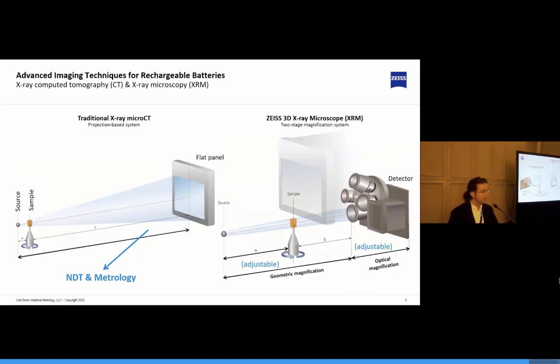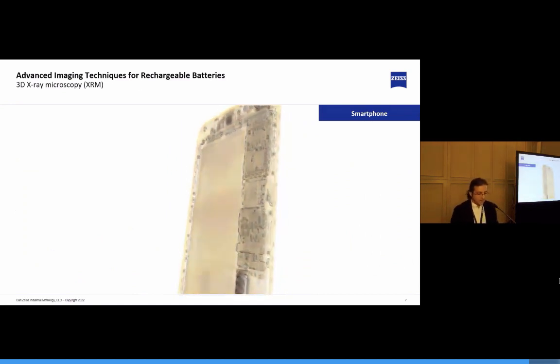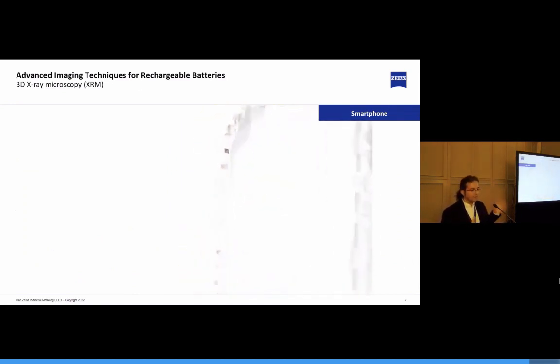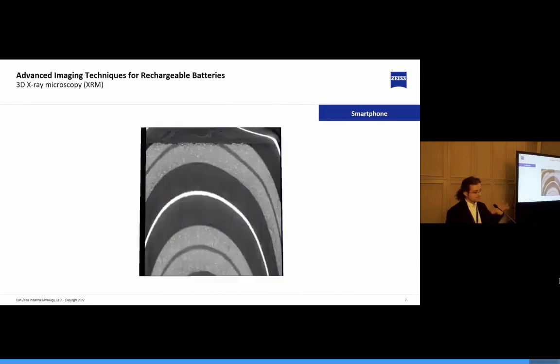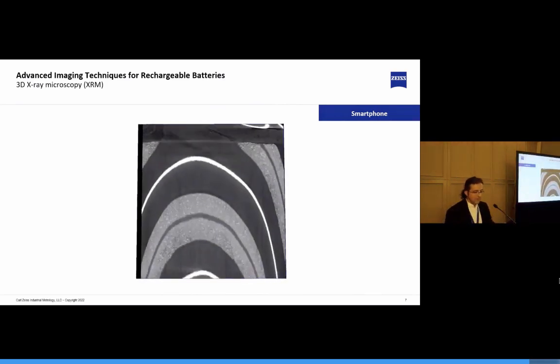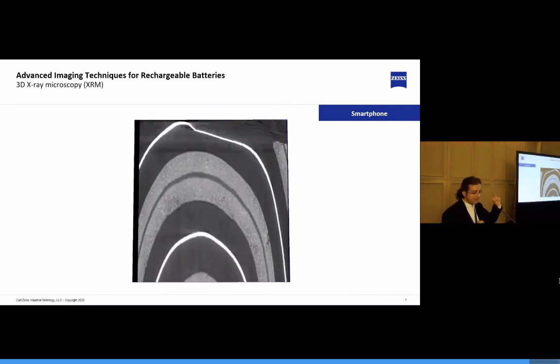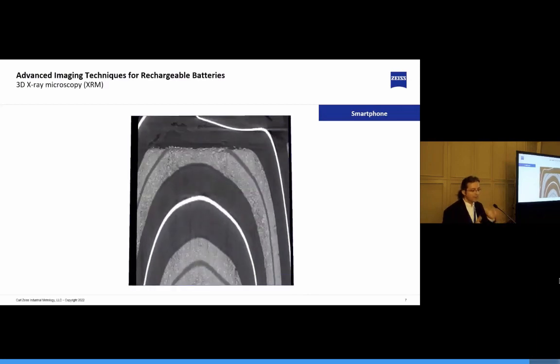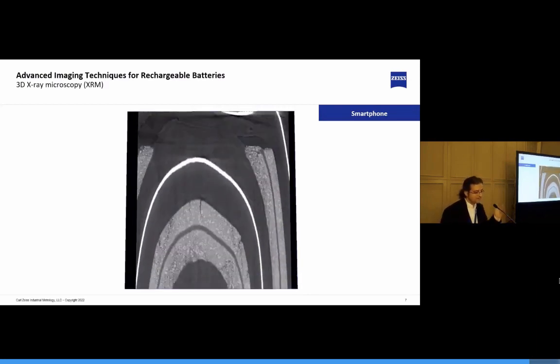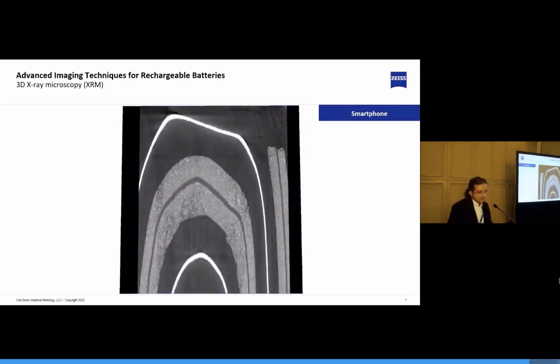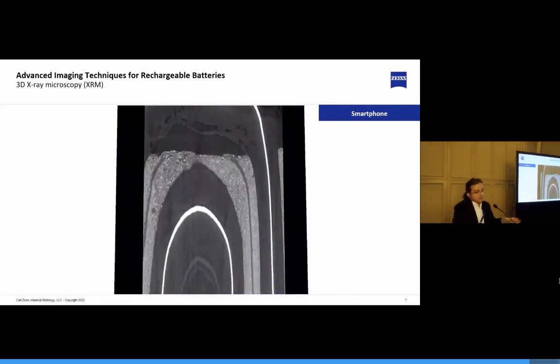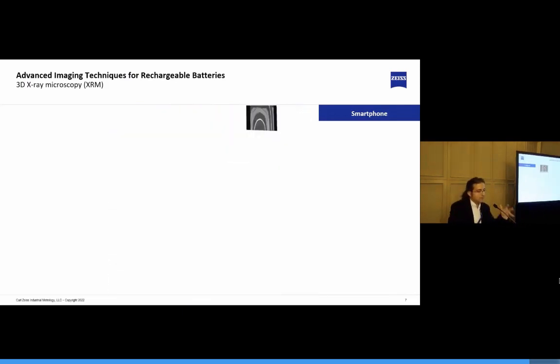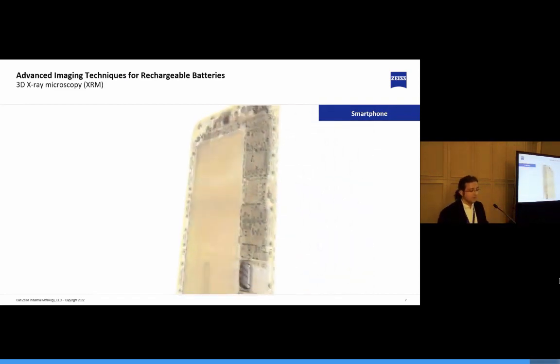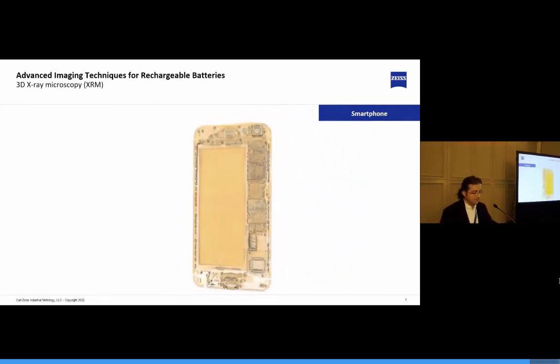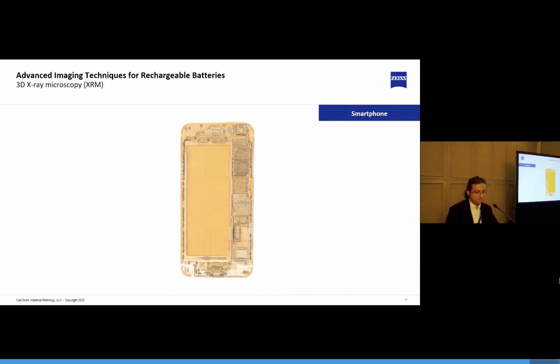This example shows how we can scan a full device, such as a smartphone, without destroying it. And then by zooming in with the lenses, we can scan small regions of interest, such as the smartphone battery, to look for any structural changes or degradation in different layers of the battery, such as cracks caused by fatigue, operation during several cycles of charging or discharging.